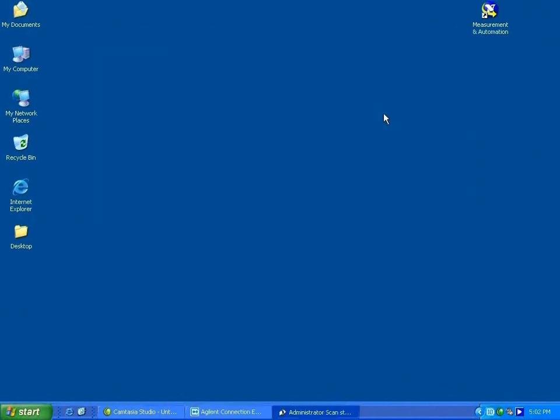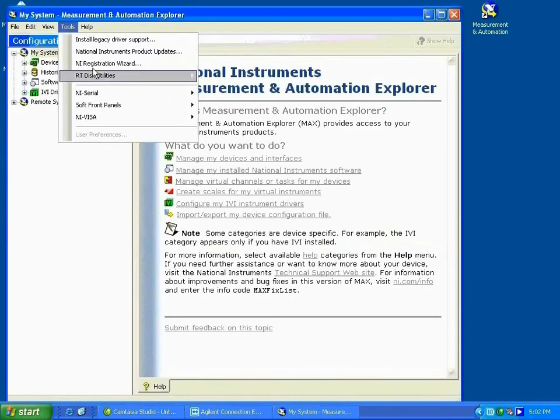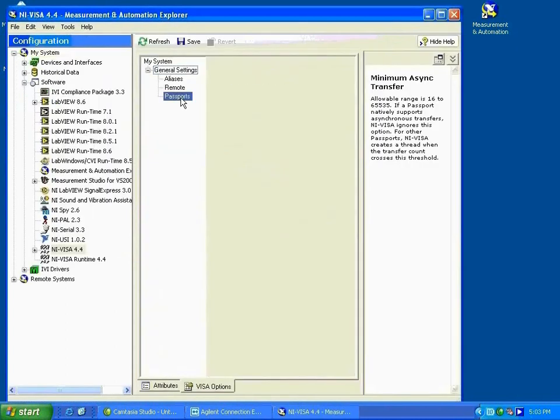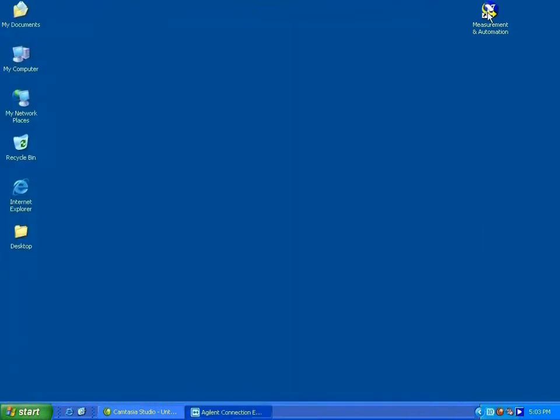The next thing you need to do is to enable the NI VISA Passport Editor in NI MAX to work with Agilent hardware. Launch your NI browser, go to Tools, then NI VISA, then VISA Options. Click on Passports. As you can see, by default the file nivisatulip.dll is not checked. Go ahead and check the box, click Save, close the browser, and restart.